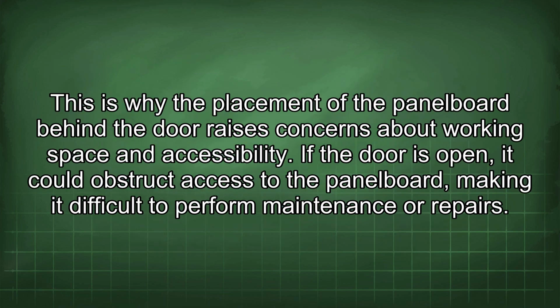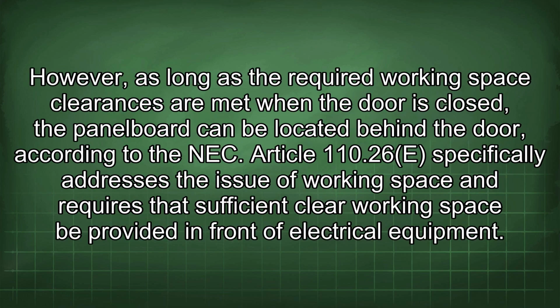This is why the placement of the panel board behind the door raises concerns about working space and accessibility. If the door is open, it could obstruct access to the panel board, making it difficult to perform maintenance or repairs. However, as long as the required working space clearances are met when the door is closed, the panel board can be located behind the door, according to the NEC.